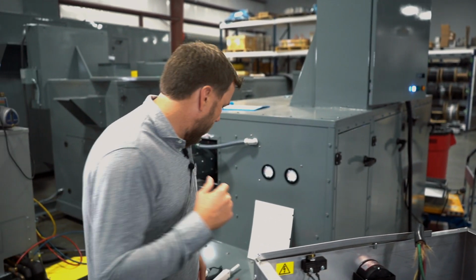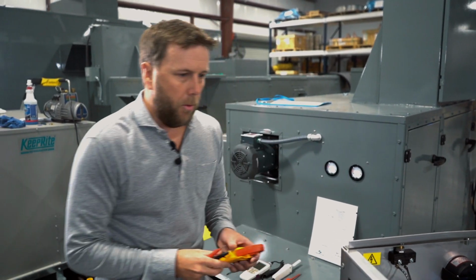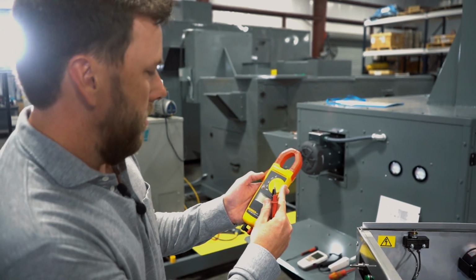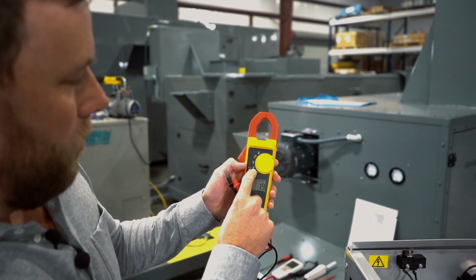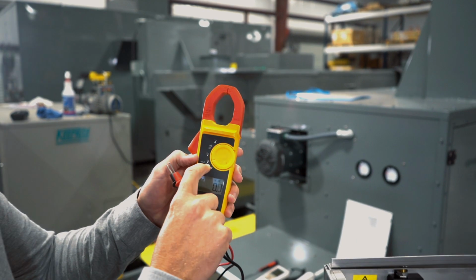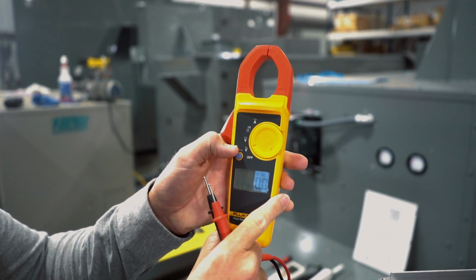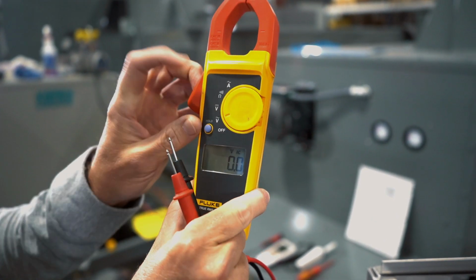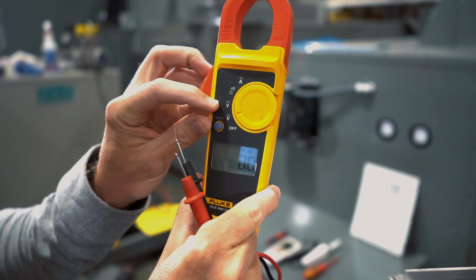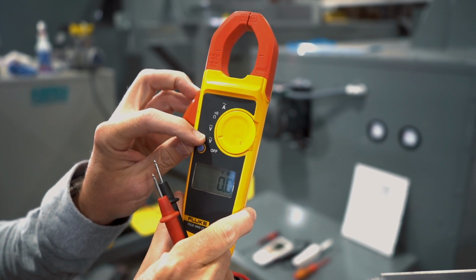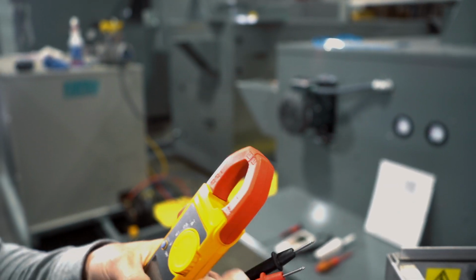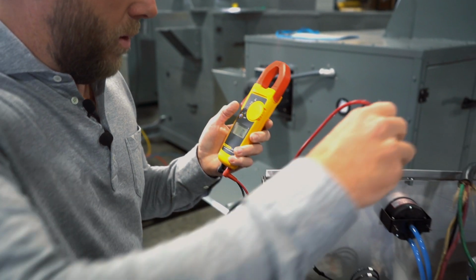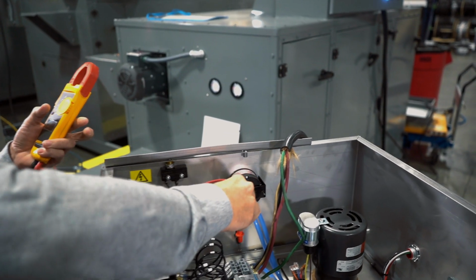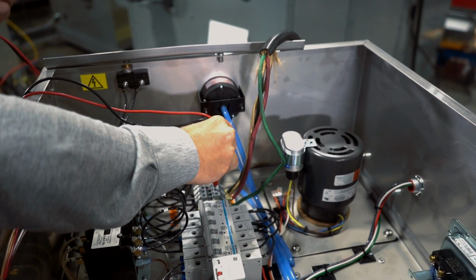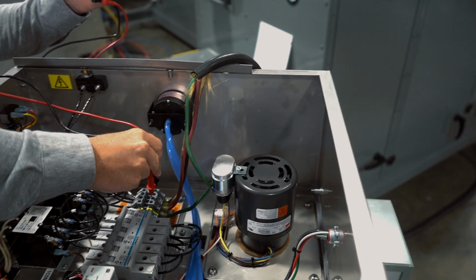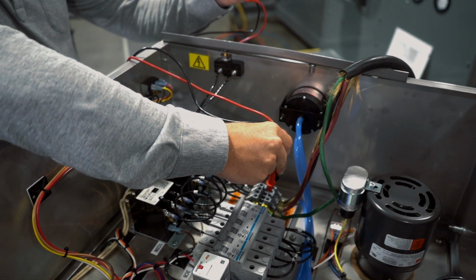Now that we have power, we want to double check that we have the proper power. With your voltmeter, turn it to the AC volt setting, which is the capital V with the curved AC indicator line. The straight line would be an indicator of volts DC. We want to set it on the AC setting since we've got 480 volt AC. In this situation, we will measure between L1 and L3 and make sure that we've got 480. In this situation, we've got 495 volts.